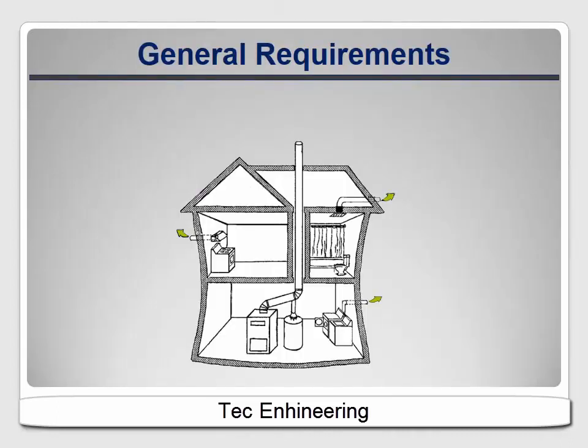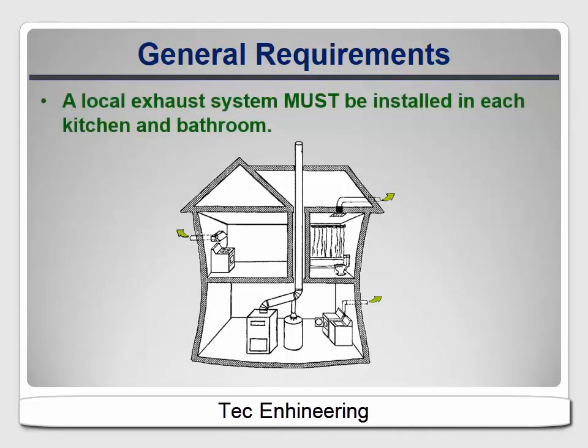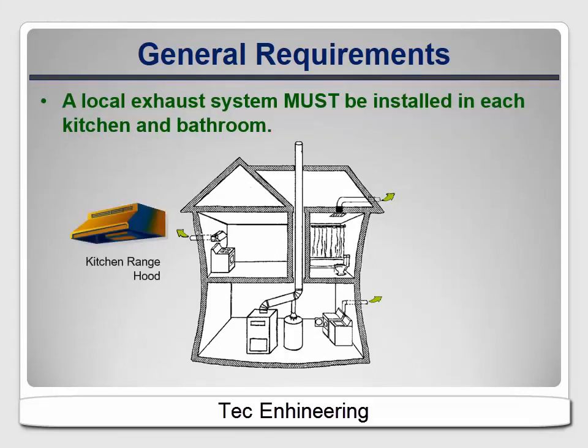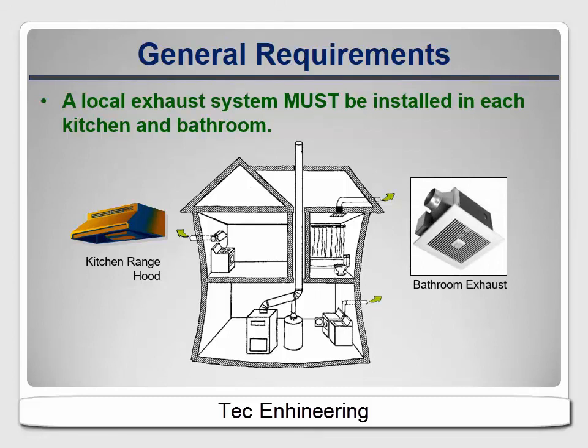ASHRAE 62.2 says that a local exhaust system must be installed in each kitchen and bath. Remember that this was written for new construction; we'll come back to the requirements for existing homes later. In kitchens, the solution is typically a range hood or a fan integrated into an over-range microwave. In bathrooms, it's usually a ceiling-mounted fan.